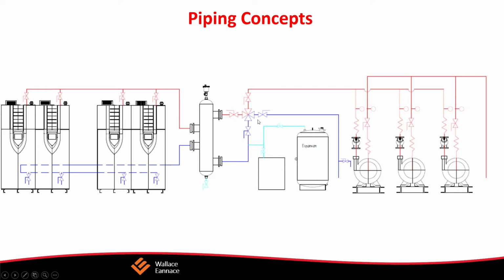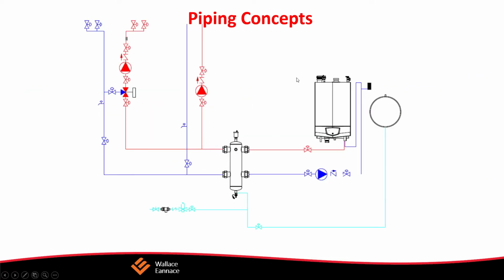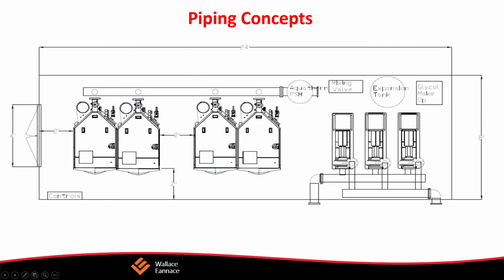Let's take a look at some more piping concepts here. What you see here is, once again, we have our primary, secondary header, a zone going out, 2 boilers. This is the first one going in here, and the return. Here you can see the primary, secondary header. You have 2 boilers, and the indirect you can see is being taken off as a zone. So sometimes you can do it on the primary side. In this particular case, we're doing it as a zone. These are fully modulating Lochinvar boilers. This is easily programmable.